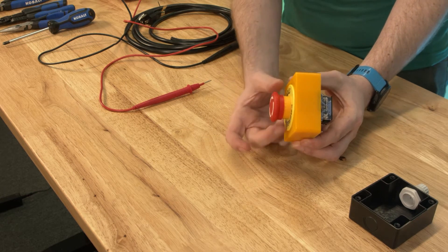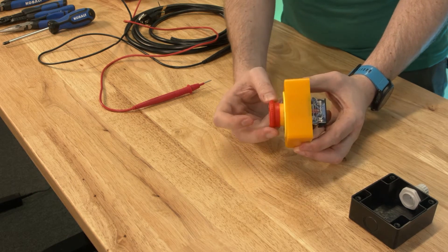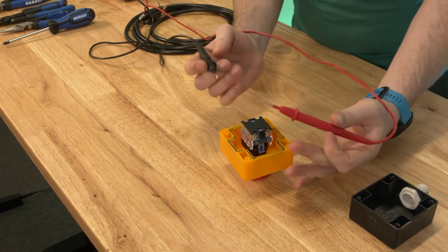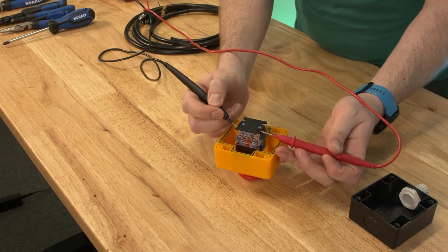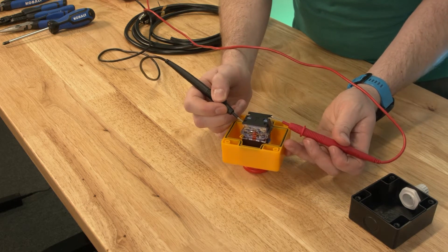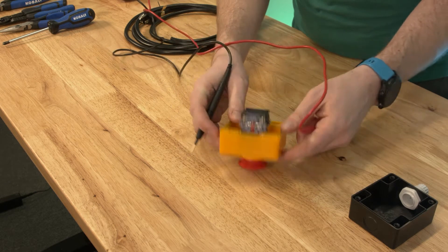So we want the machine to only run when the button is out, and we want to turn it off when the button is in. So we're going to pull the button out, we're going to use our multimeter here to double check the continuity, and as the spec sheet says, the contacts labeled one one and one two here are energized, or they are closed, when the button is out.